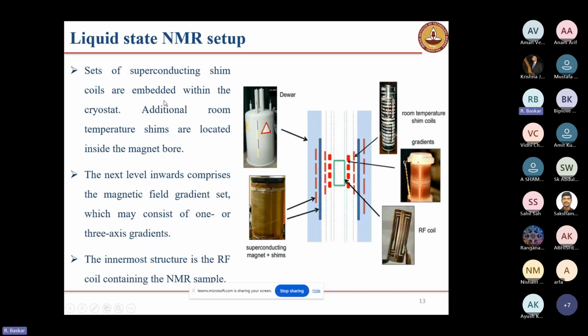Sets of superconducting shim coils are embedded within the cryostat. This is the superconducting coil, and in addition, shim coils are there. I'll explain later what shimming is. Some of the shim coils are present in the liquid helium itself. That is called the cryoshims. They make the magnetic field homogeneous in the sample area.